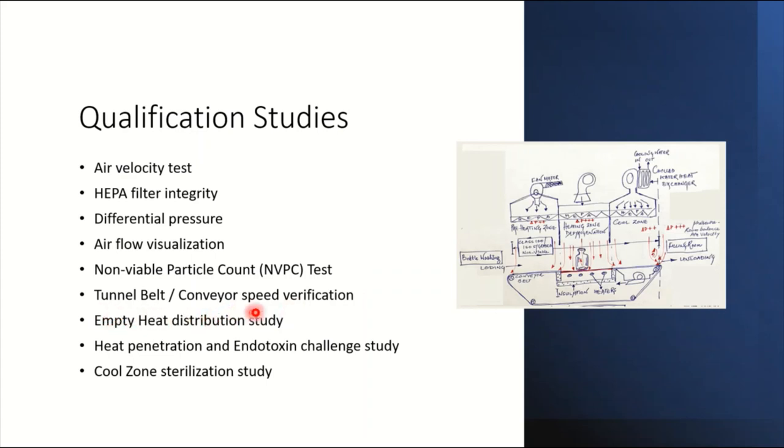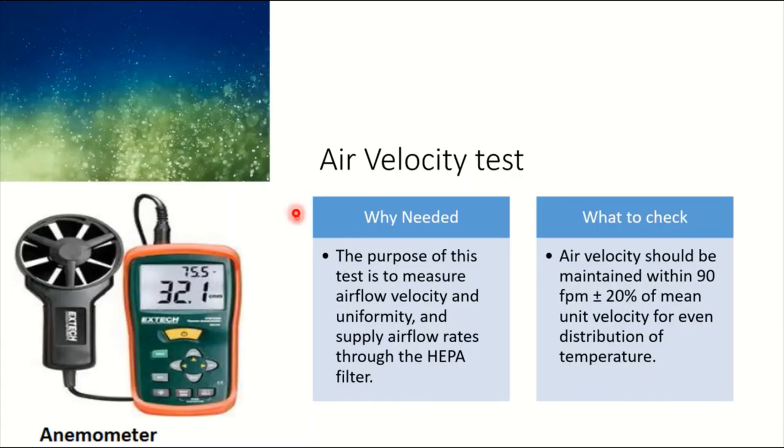Tunnel belt or conveyor speed needs to be verified because you need verified speeds. When placing vials with different diameters and configurations, you need to ensure the speed is maintained. Empty heat distribution study is important to see if distribution is uniform. Heat penetration and endotoxin challenge study is very important—it will give you thermal data and help understand how much endotoxin reduction we're getting. The last study is cool zone sterilization.